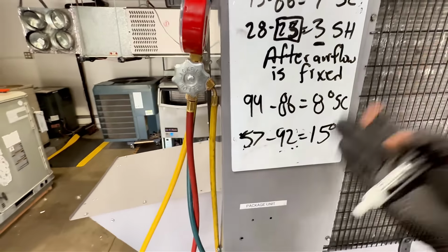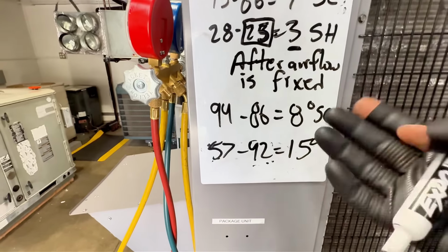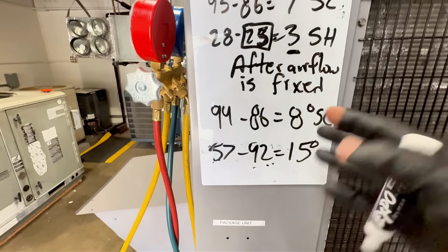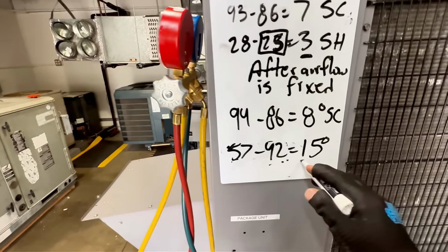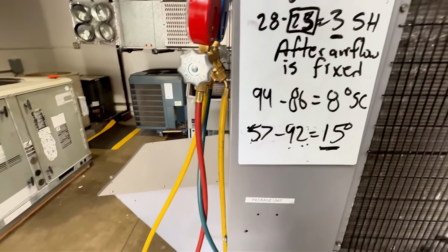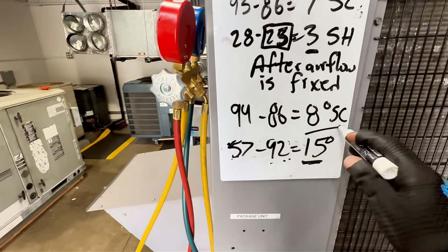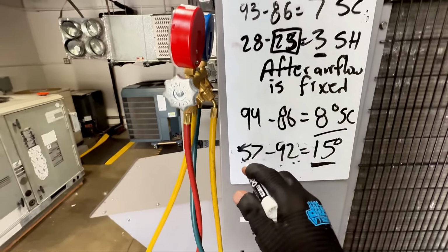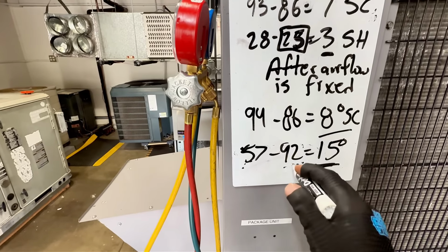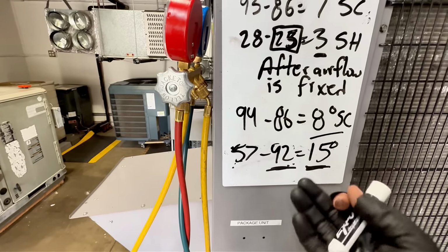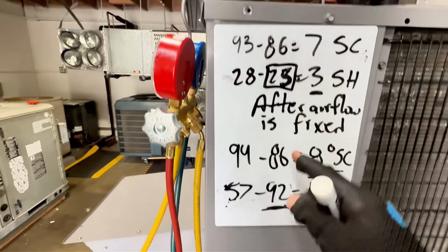Am I okay with that? Yes, I can live with that. It's 8 to 14, right? 8 to 14-ish, around there. I'm okay with this. I'm good. My subcool's good. My superheat is good. My evaporator temperature makes sense because now I'm introducing more warm air. Remember when I had low airflow, it was 25 degrees? There's no air.